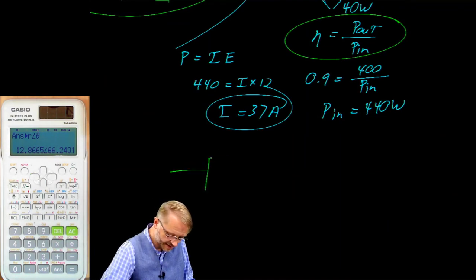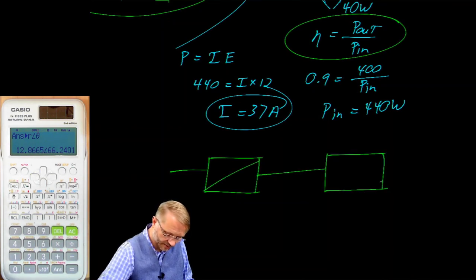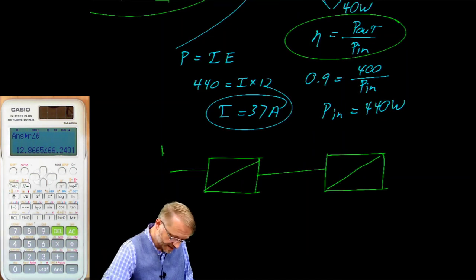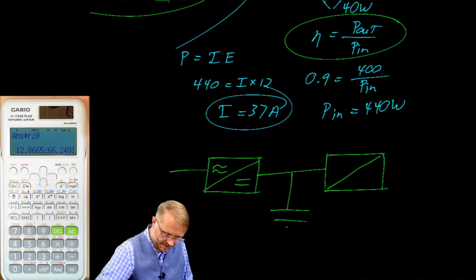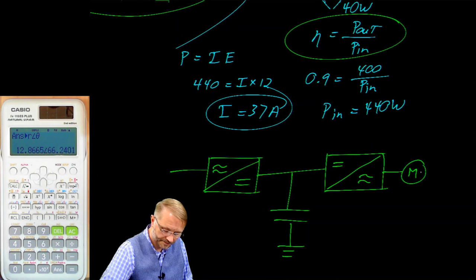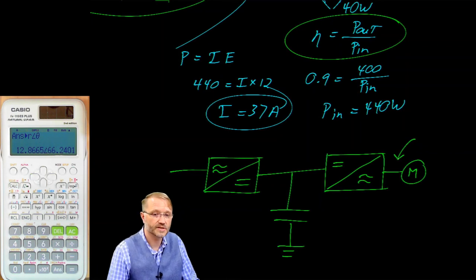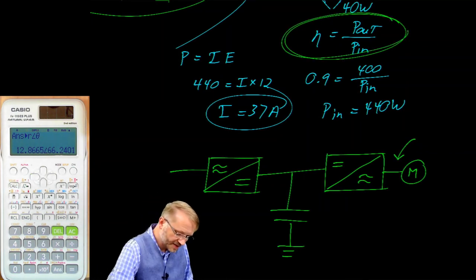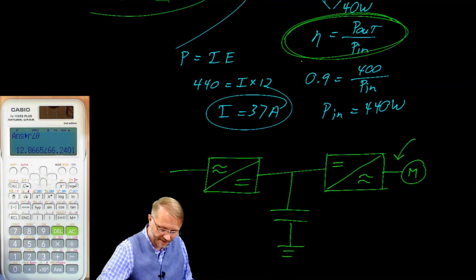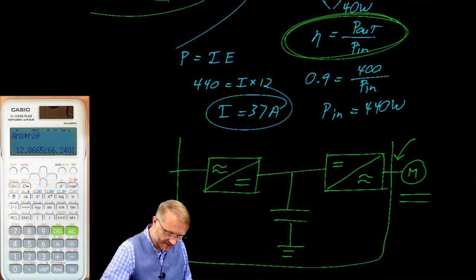Because at some point in the near future, we are going to encounter something called a variable frequency drive. What it does is it takes in AC voltage, converts it to DC. We have a large storage capacitor here to smooth everything out. Then we take DC and we convert it back into AC to drive a motor. Except this time, this AC, you can change the frequency, which means you can change the speed of the motor. I bring up efficiency because we're going to chain these together. We're going to talk about the efficiency of the motor and then we can talk about the efficiency of the variable frequency drive.